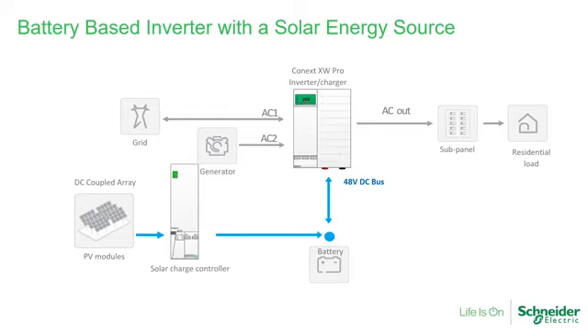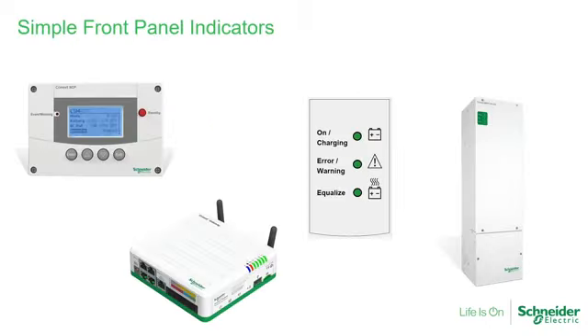The idea of having the solar charge controller and the inverter together in the same network is now that the inverter can get information from the charge controller and decide to start exporting power out to the meter earlier, what we call enhanced grid support. For the MPPT80, what you see in front of the unit, you see these LED lights. So it doesn't have a UI or user interface. And you have heard me talk about programming, and there's some programming requirement, and I'll show you what that is.